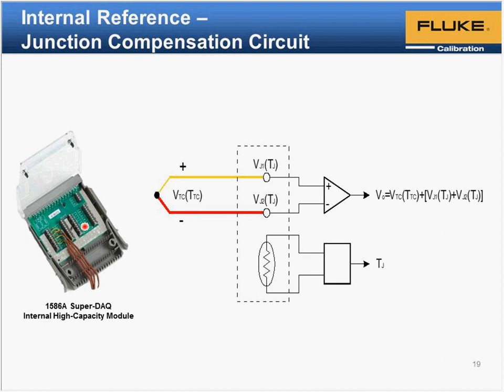This is a picture of one of the Fluke products. It's a high capacity module. So the temperature sensor is right here in the center, but thermocouples connect on several different terminal blocks on this card, and the specs on this thermocouple compensation circuit, reference junction compensation circuit, are fairly large because there's so much space separating where the thermocouples connect versus the temperature sensor. But the goal with this one is to have high capacity to be able to connect lots of thermocouples to it.